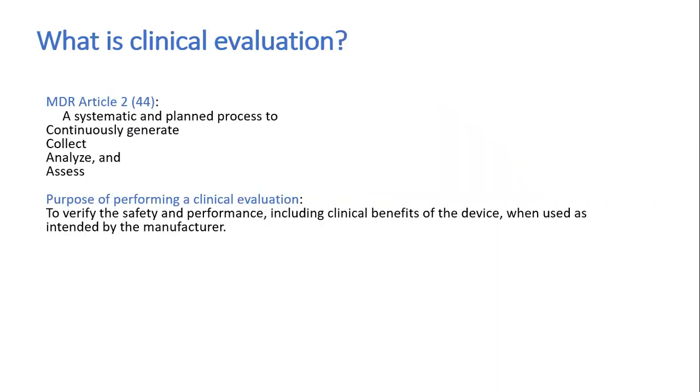So what is the clinical evaluation as per MDR Article 2(44)? It's a systematic and planned process to continuously generate, collect, analyze, and assess the data. And what is the purpose of performing a clinical evaluation? To verify the safety and performance, including the clinical benefits of the device when used as intended by the manufacturer. So we're performing clinical evaluation to establish the safety and performance.